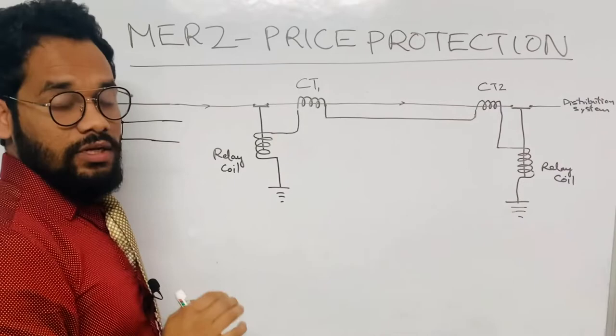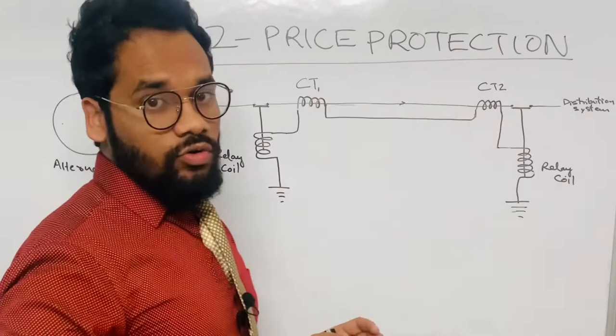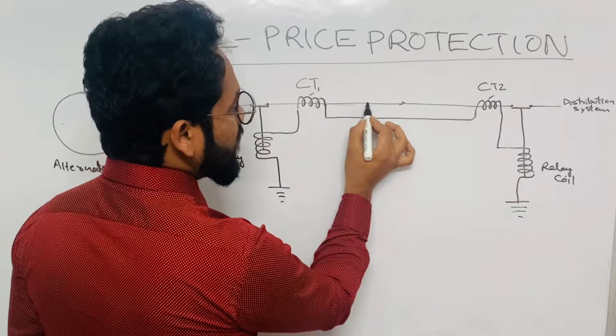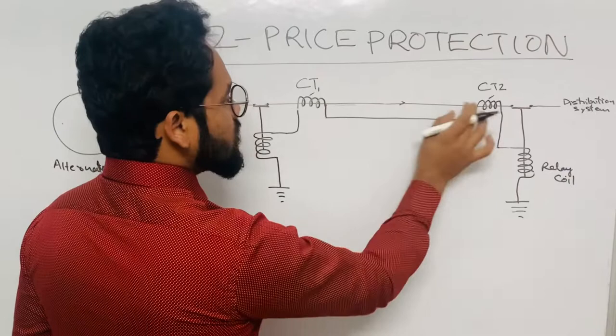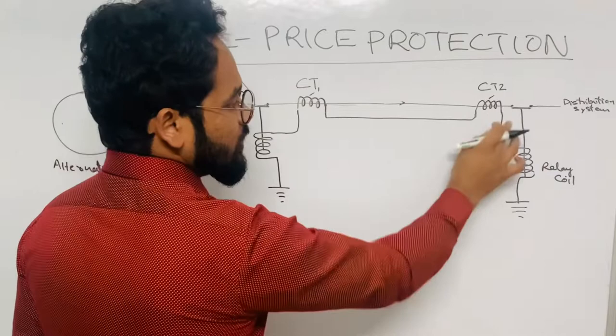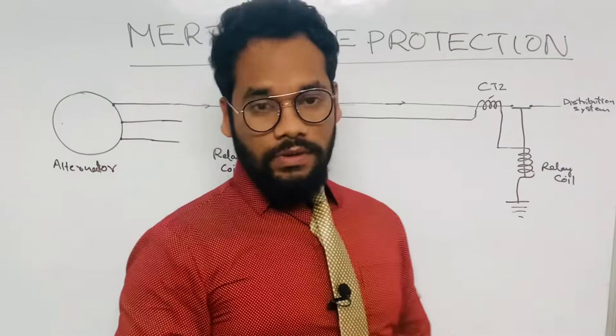In the normal scenario, since the induced EMF in CT1 and CT2 is the same, the potentials at both points are equal. When potentials are the same, no current flows between them. So no current will flow through the relay coils, and hence both relay coils will not be energized. The system keeps operating normally.